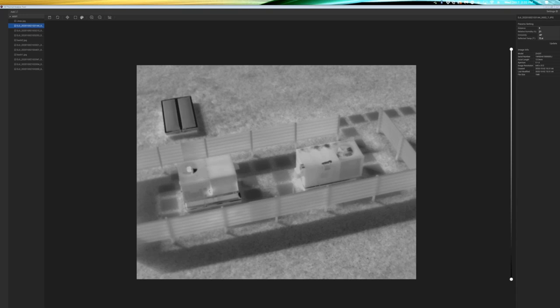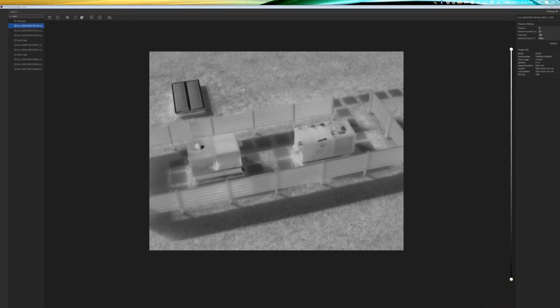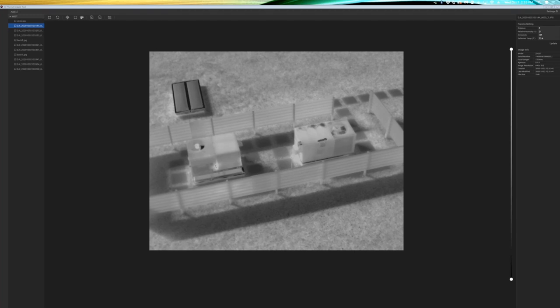Sebastian, is it possible to analyze videos? No. A video does not contain radiometric data. It would make videos monstrous. Because every frame would have to have temperature data on every pixel. So no, you cannot analyze videos. You can only analyze photos. Because literally every pixel represented has its temperature data. Now, if we compare a 640 by 512 JPEG to a radiometric JPEG, right? Now, a typical JPEG of this size is going to be probably around 30K, right? The radiometric JPEG is about a meg. So a lot of data is stored in these images.